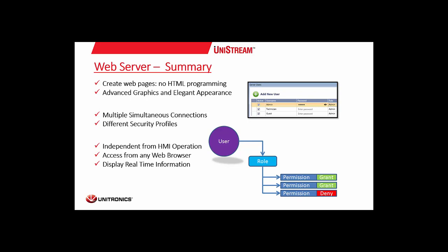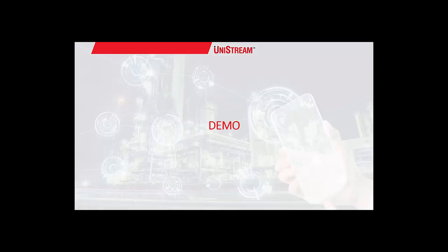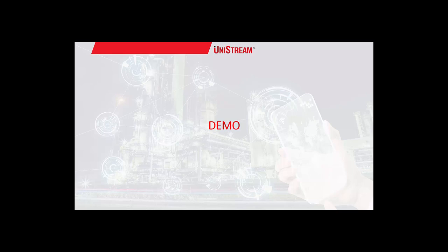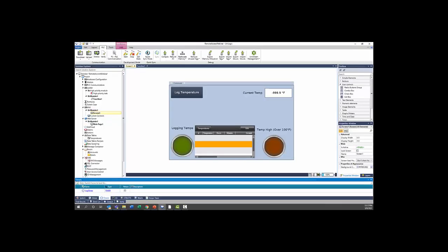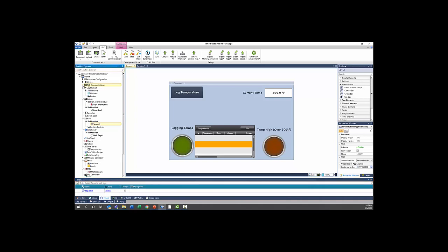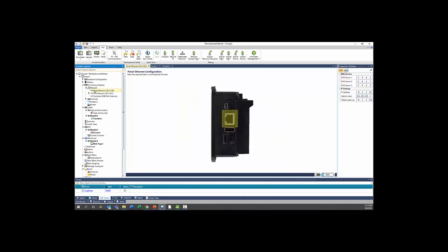And now we're going to take a look at an example project for Unilogic. So here I have a little basic program set up. For this, we're just going to start by taking a look at the remote connection. To set up your remote connection, you're going to go to PLC communications, then physical, and the IP address that matters for your remote connection is going to be the panel Ethernet. So I have that set here. You also want to configure DNS servers. The two DNS servers you see here are Google's free DNS servers. This will allow the PLC to connect outside of your local network and connect to the internet in general.